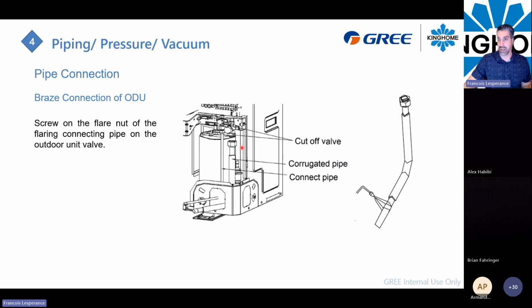At the outdoor unit, the 3-ton unit, the connection and the valves are inside the cabinet. It's the only unit that has this type of connection, but you will have to bend your piping inside of the cabinet, and the connection will be inside the panel right here. You will have your liquid service valve and suction service valve, and you will have to flare your 3/8 and 3/4 pipe directly inside the unit.